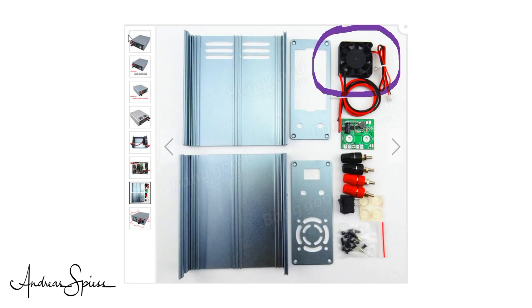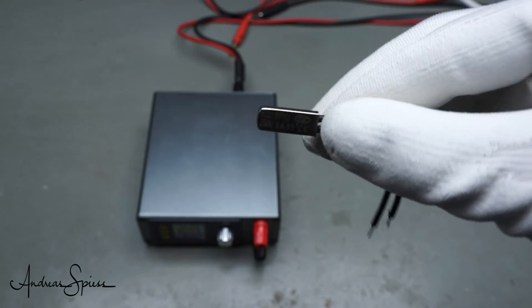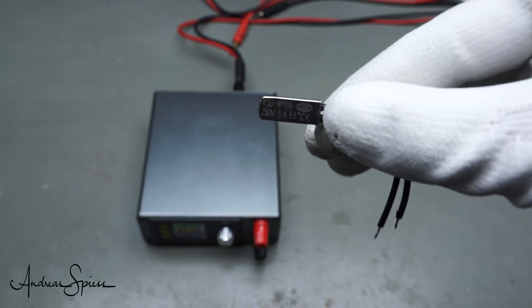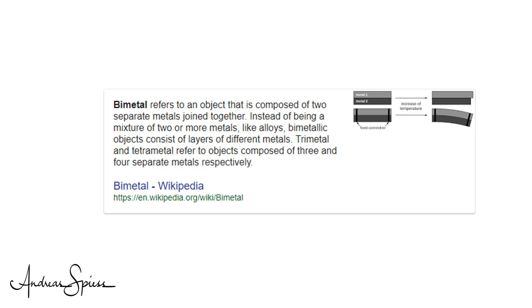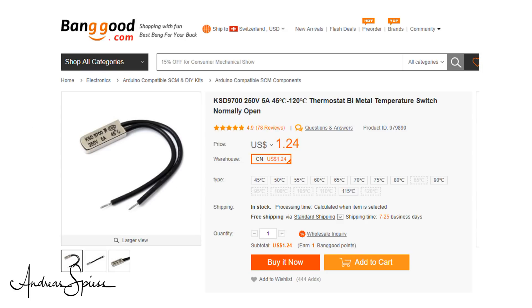The simplest way to achieve this is to use a bimetal switch. Bimetal switches, as their name suggests, consist of two metals welded together. Often the materials are steel and copper. If heated, the different coefficients of thermal expansion makes the strip bend. And this bending is used to open or close an electrical contact, very similar to a relay. Because the surface of the contacts is quite big, the on resistance is low, and the maximal current which can be switched is 5 A.